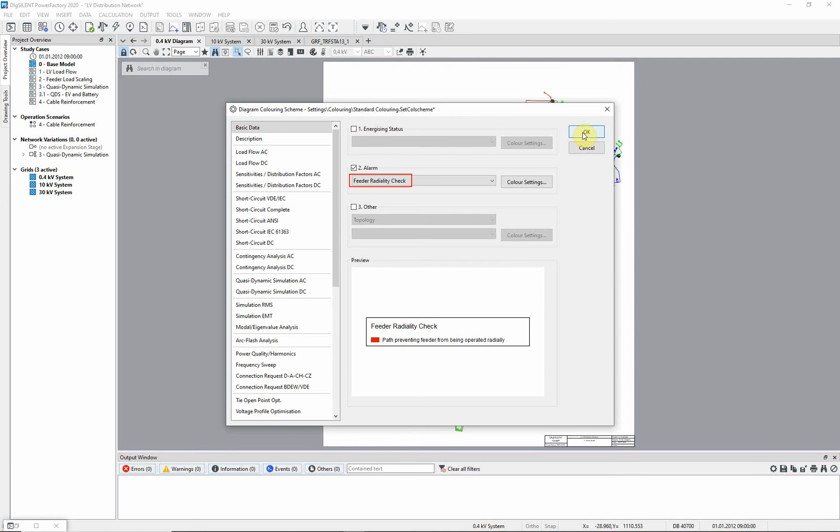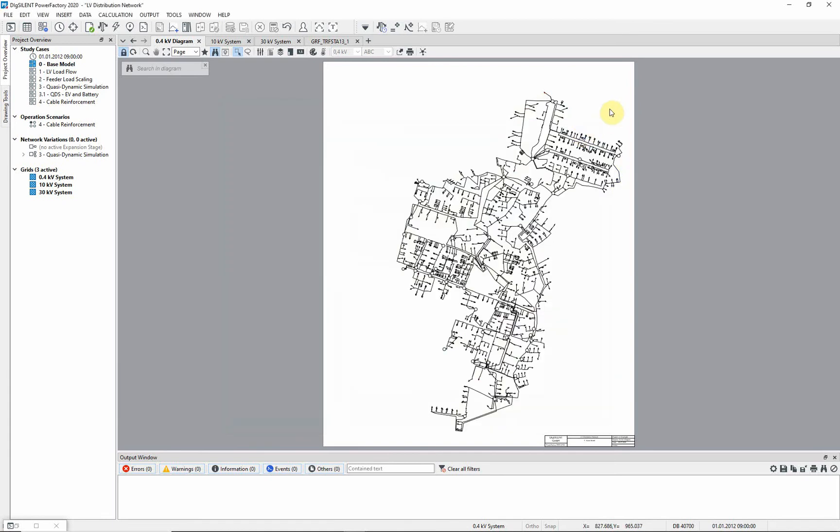Notice that with this option checked, any feeders that are not being operated radially will be highlighted in bright red. None of the feeders are shown marked as bright red, therefore it can be assumed that the network is running radially. We will now close an interconnection and force the network to run in a mesh.